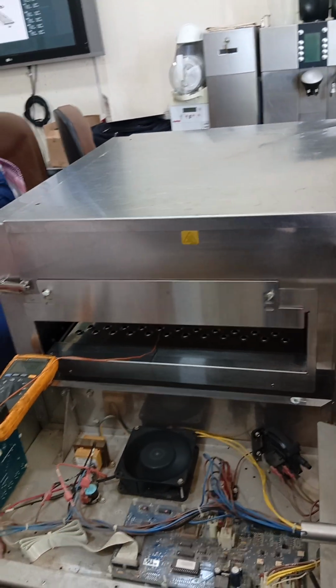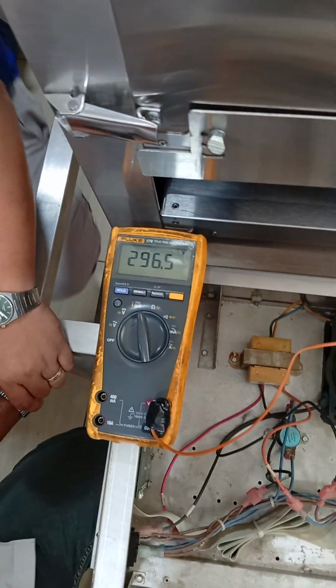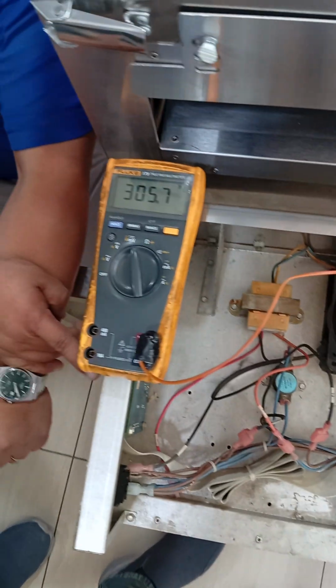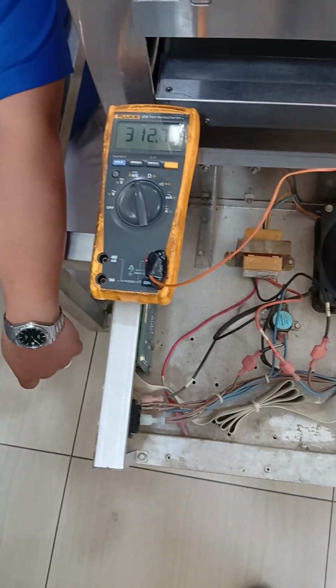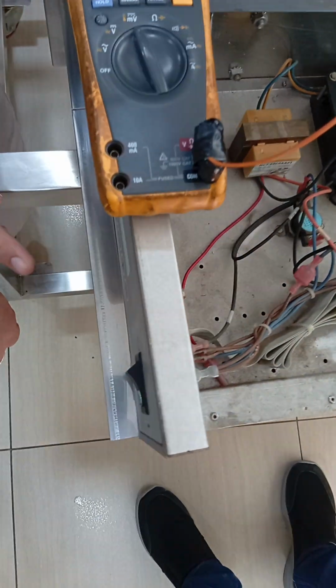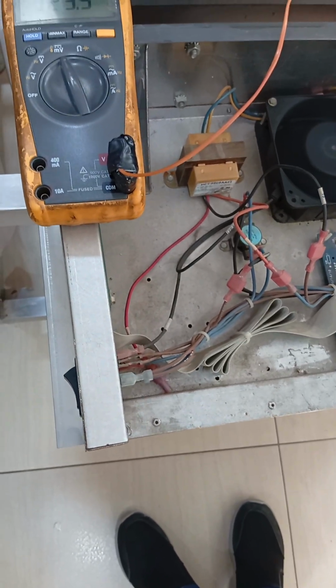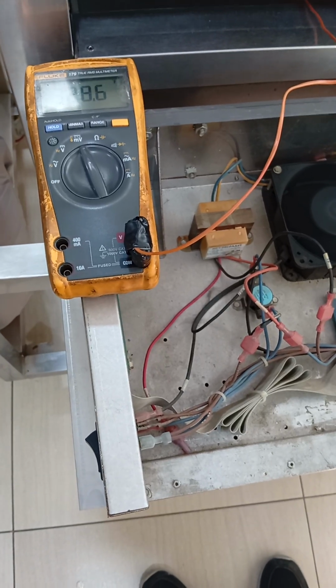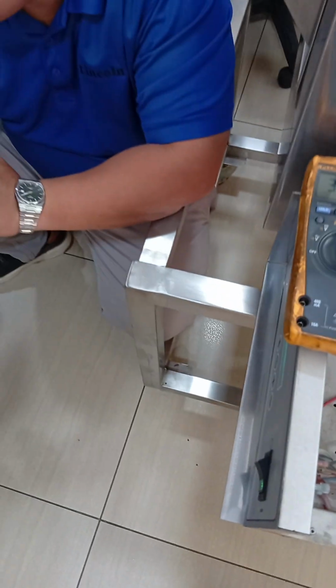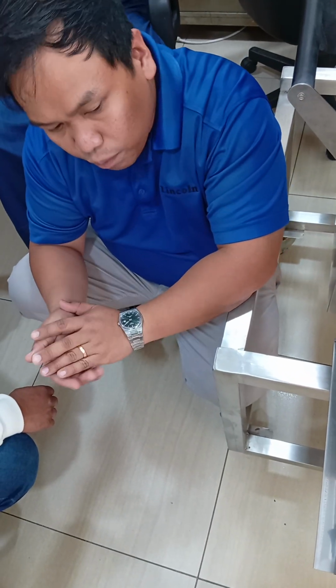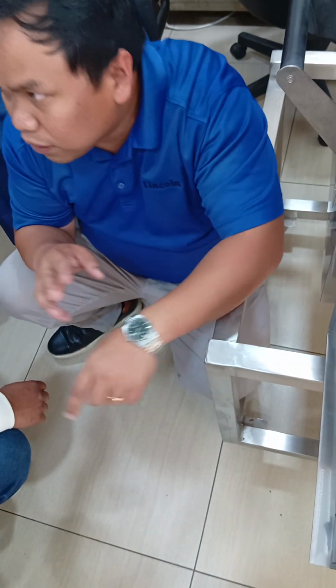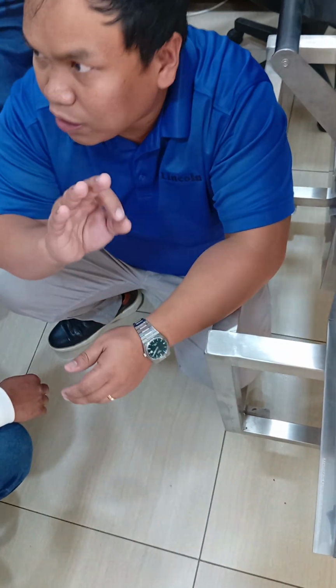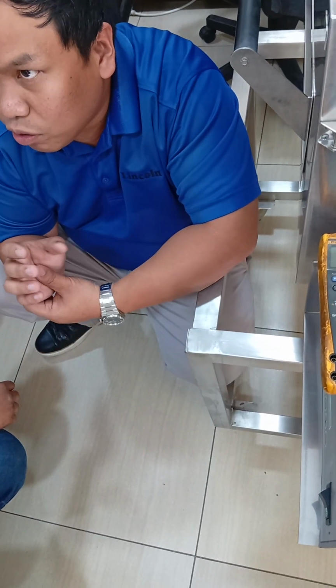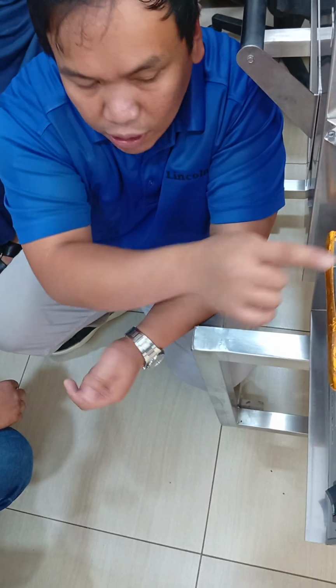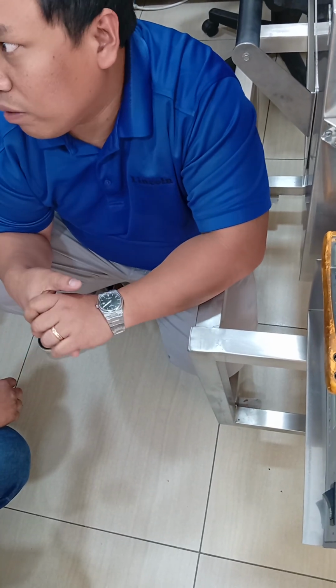Okay. So 290, now 290, 290. Here it's visible that it's heating. Because with this type of display, you have only one temperature probe. Then on the display, there is a space to show heat. Okay? But with 2 temperature probes, what you will notice is there is HL and HR. Okay? Meaning HR or HL is heating on the right or the left. Before you get the actual reading, make sure both HL and HR, or heat, are off. Meaning it's not on the display. Okay? Meaning that the cavity has now achieved the set temperature. Then you will verify if your actual and display readings are the same, or plus or minus 5. Okay?